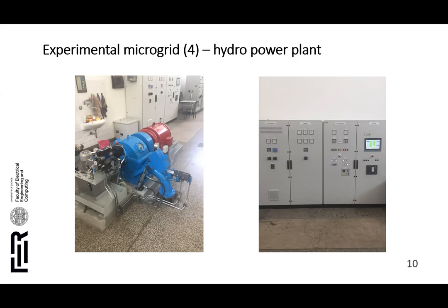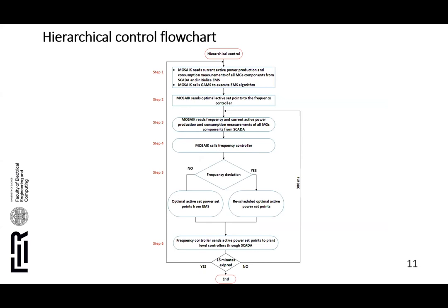This figure shows the working principle of the hierarchical control approach. The entire operating procedure consists of six steps. Step one is conducted every 15 minutes: the co-simulation framework reads current active power measurements, initializes the upper optimization control algorithm, and executes it in a general algebraic modeling system. The results are optimal active power set points for each control unit for the next 15 minutes. In step two, MOSAIK sends these optimal active power set points to the frequency controller.